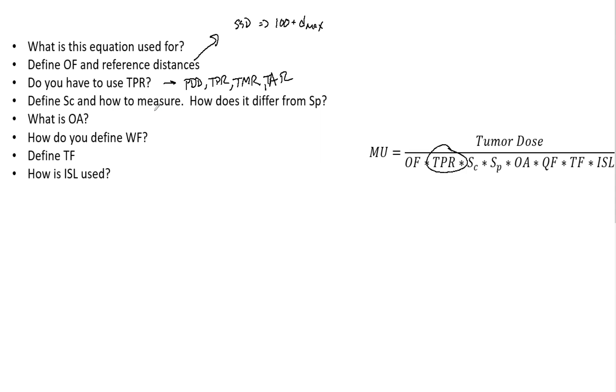Mainly because the 10 by 20 and the 20 by 10, there's different backscatter toward the MU chambers, and that affects the output.